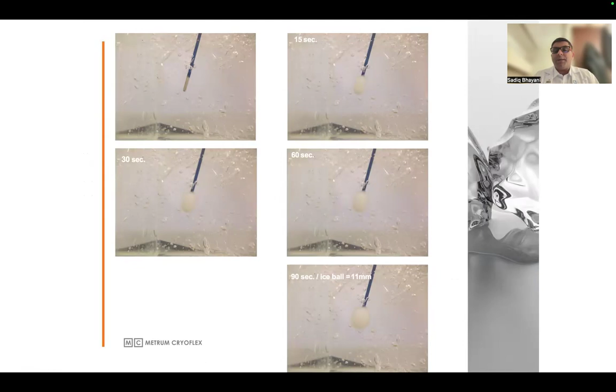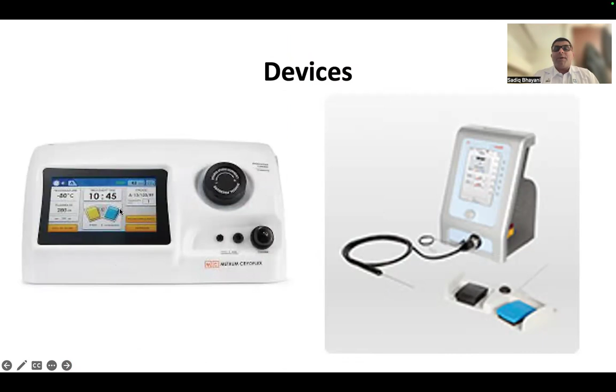This is around a 1 centimeter big ice ball that you can create using a 16 gauge, 18 gauge cannula. And what's in the device? Basically, the device has a touch screen. Inside the device is a gas cylinder which is attached to the device. You have a gas flow monitor, the thermistor to monitor the temperature, and you also can do stimulation, like sensory stimulation or motor stimulation, to know that you're close to the nerve.